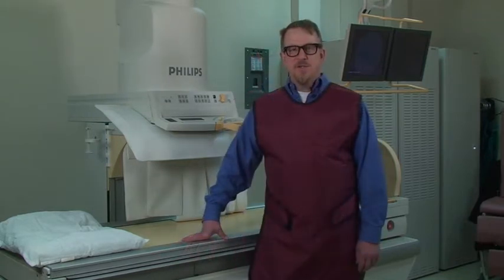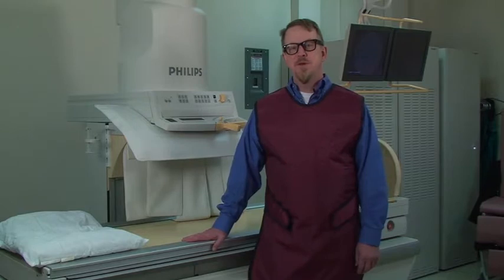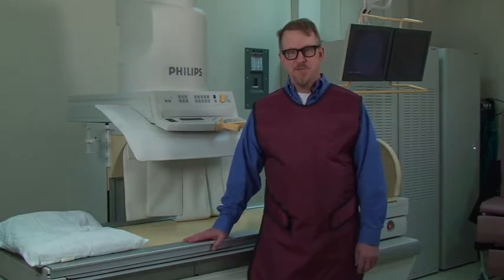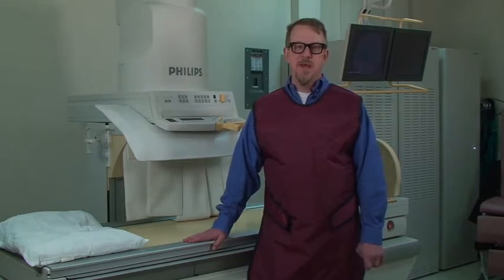The pedal is called a dead man switch because the beam will stop if pressure on the pedal is removed for any reason. There also will be an exposure button on the tower or the table console of the fluoroscope that the radiologist may prefer to use, and it must be continuously pushed. The fluoroscopic tube also has the option for a pulsed beam for fewer frames per second. For general fluoroscopy work, this will not interfere significantly with the diagnostic quality of the test. However, it will reduce patient dose and scatter production as a result.